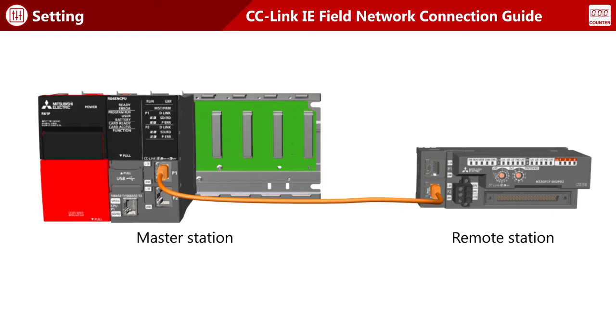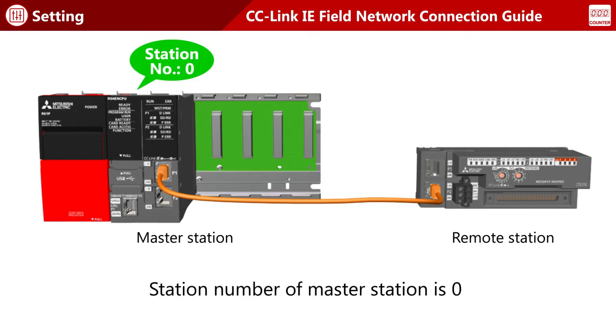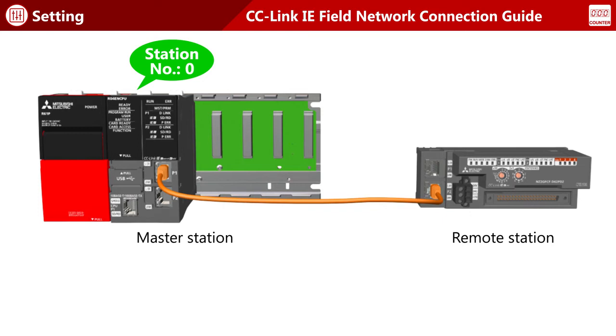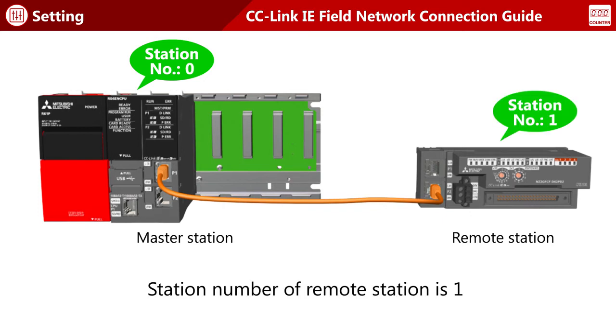The system shown here is configured with two stations. The station number of the master station is always fixed to zero. For the remote station, set the station number to one.